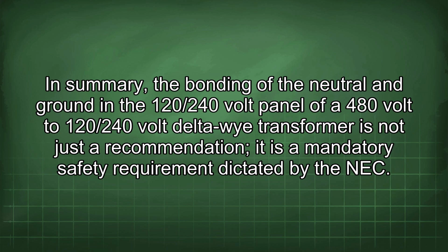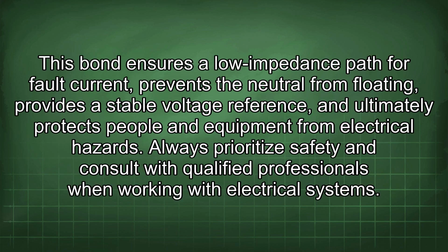In summary, the bonding of the neutral and ground in the 120/240 volt panel of a 480 volt to 120/240 volt delta-wye transformer is not just a recommendation, it is a mandatory safety requirement dictated by the NEC. This bond ensures a low impedance path for fault current, prevents the neutral from floating, provides a stable voltage reference, and ultimately protects people and equipment from electrical hazards. Always prioritize safety and consult with qualified professionals when working with electrical systems.